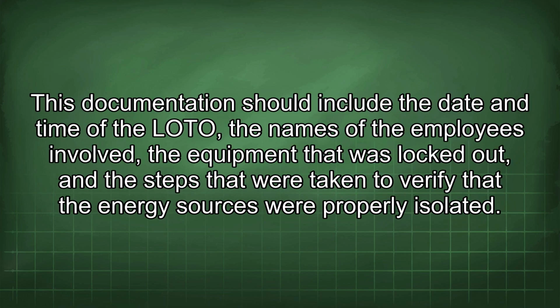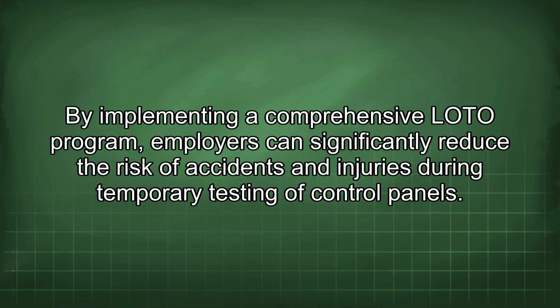activities. This documentation should include the date and time of the LOTO, the names of the employees involved, the equipment that was locked out, and the steps that were taken to verify that the energy sources were properly isolated. By implementing a comprehensive LOTO program, employers can significantly reduce the risk of accidents and injuries during temporary testing of control panels.